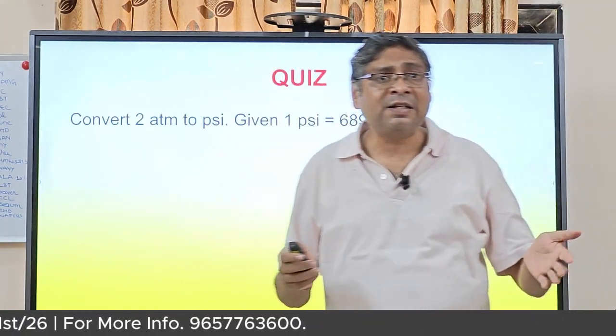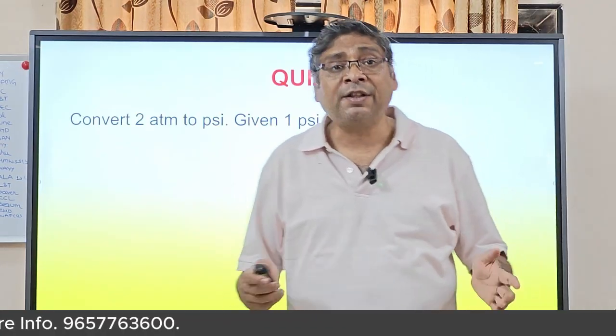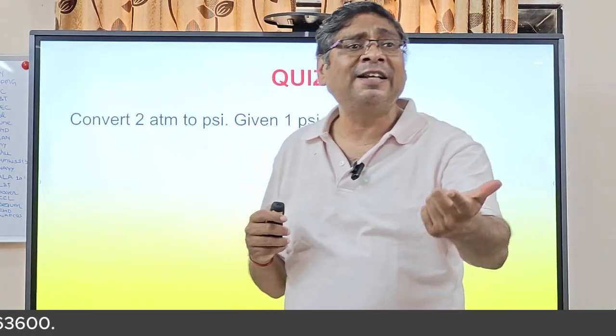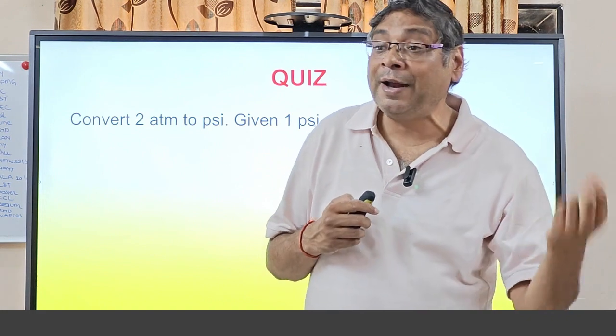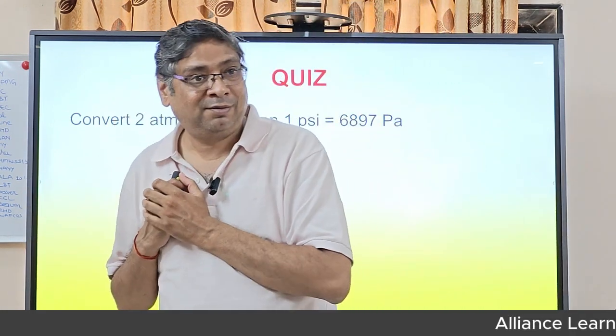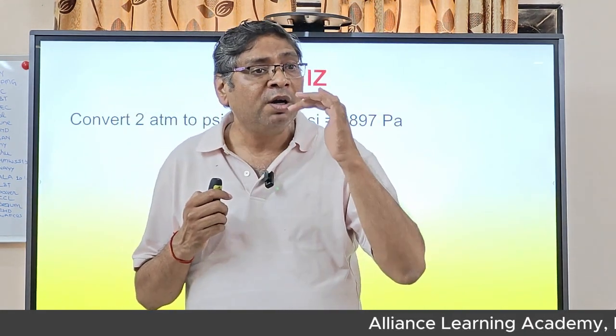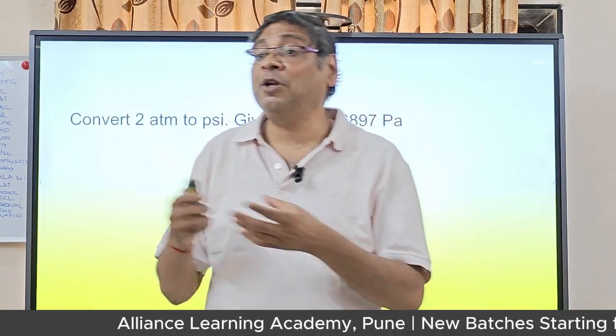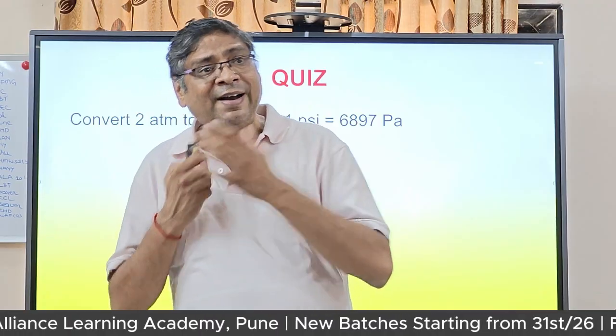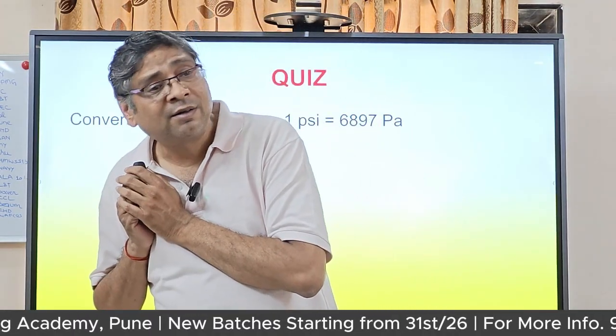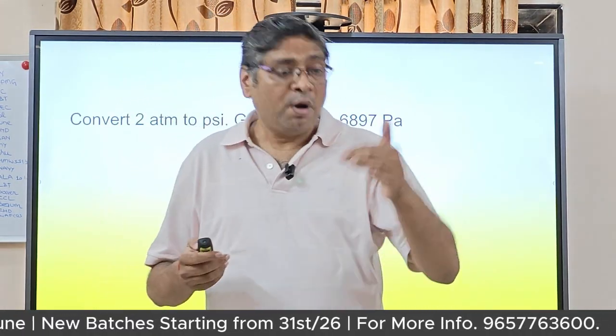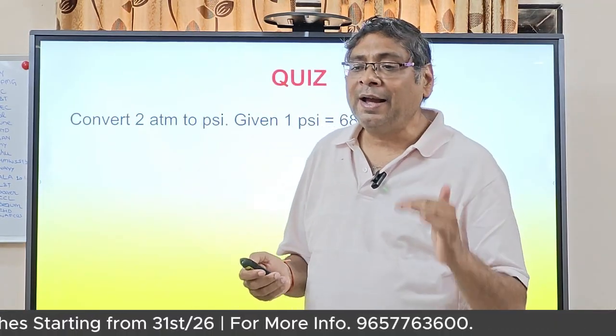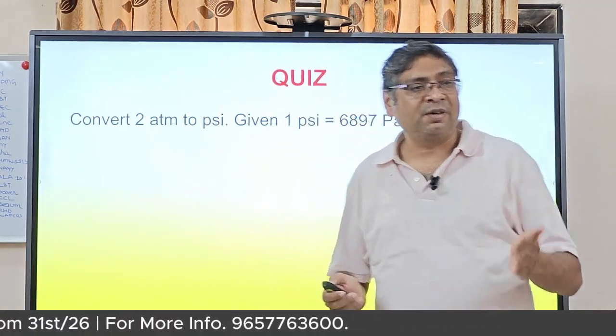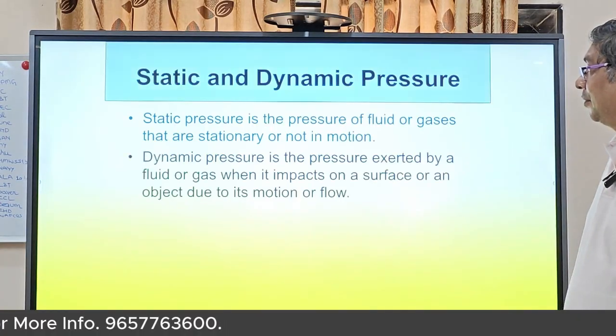From the control valve point of view, they will ask what is the pneumatic pressure for a control valve - 3 to 15 PSI. Can you convert that to kg per centimeter square? It's 0.2 to 1 kg per centimeter square. So these conversions should be on your fingertips - 1 ATM equals how much Pascal, 1 ATM equals how much kg per centimeter square. If you don't know, write it down on a page and review it many times so you remember.